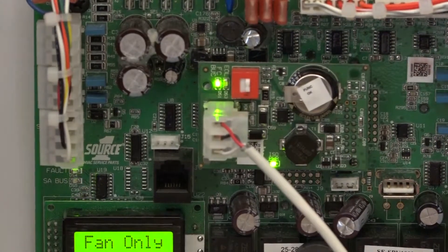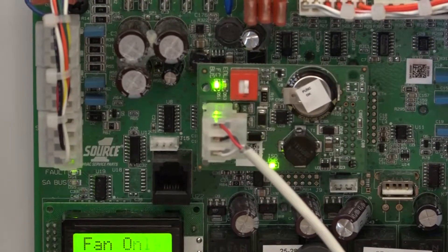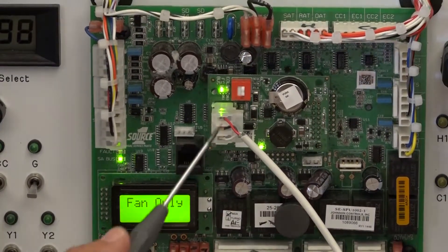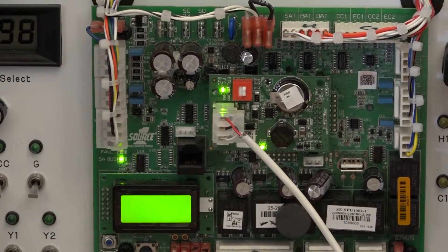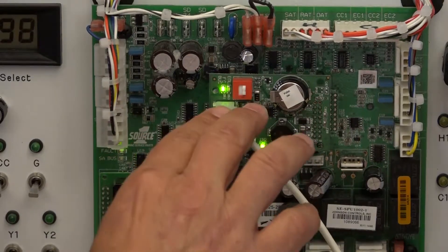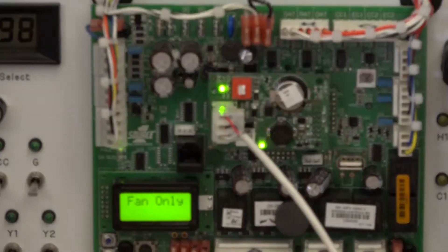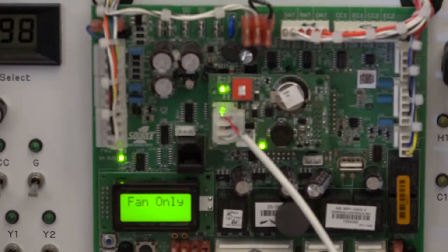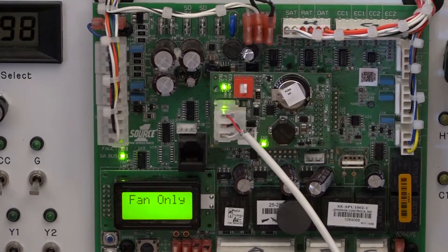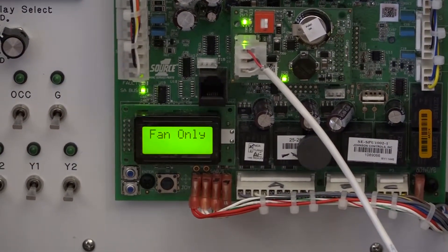Depending on the configuration of the network and the length of the wire, we do recommend the shield wire, but in most cases you can get away with the 3-wire communication. So this plug goes in here and then you've got your wire connection. Before I connect it to any other part of the Verasys system, I need to make sure the addressing and configuration of the BACnet controller — which this is — is correct.